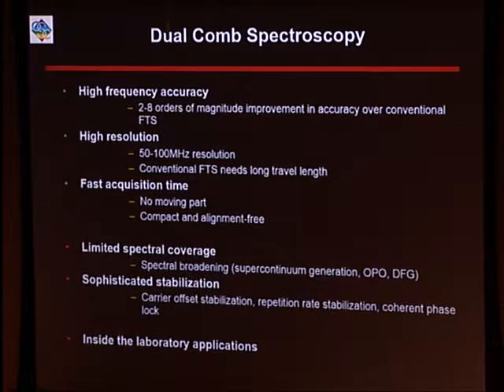But there are some drawbacks that we are trying to solve right now. There is limited spectrum coverage when you generate these femtosecond laser pulses. The output spectrum of these is narrow, so you can measure only quite a narrow spectrum at a time, right? So right now we're working on supercontinuum generation to broaden that coverage. It's also quite difficult to do dual comb with two separate lasers because you have to phase lock them, right? You have to stabilize them and make sure they are coherent with one another. That's why you need a lot of electronics in there. Our solution is to use the comb that's generated out of a single cavity, and I'll show you in the next slide.